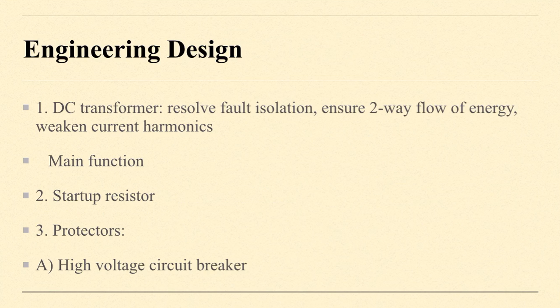And the third is protectors. First is high voltage circuit breaker. Actually, the high voltage DC circuit breaker with dual functions, control and protection, has become a bottleneck, restricting the development of VSC HVDC transmission systems. Overall, the hybrid high voltage circuit breaker is proposed with high current carrying and isolation capacity and breaking capacity. This new type circuit breaker is gradually becoming the first choice of VSC HVDC transmission projects.